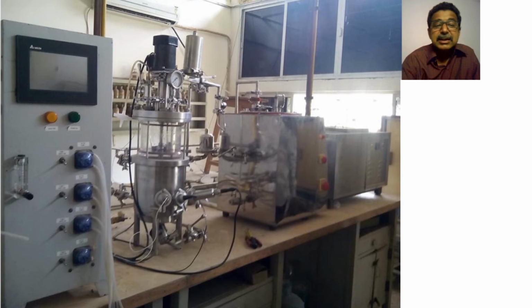So how is it controlled? The peristaltic pumps are connected, and if the pH is dropped by acid production inside by the microorganism, then the pH changes from 6.5 to 6.4, 6.3, 6.2. Immediately this PID control will switch on the alkali pump, and this peristaltic pump starts rotating and adds alkali to the vessel, so your pH shoots up slightly and comes to 6.5 again. Then this alkali pump stops. Now suppose alkali is produced inside, then it goes the other way, where the acid pump is started and acid is added, so as to bring down the pH. So ultimately you need not worry; once you start the fermenter, this machine is automatically going to control the pH. The pH probe will sense the pH, and then the controller is going to control the pH.